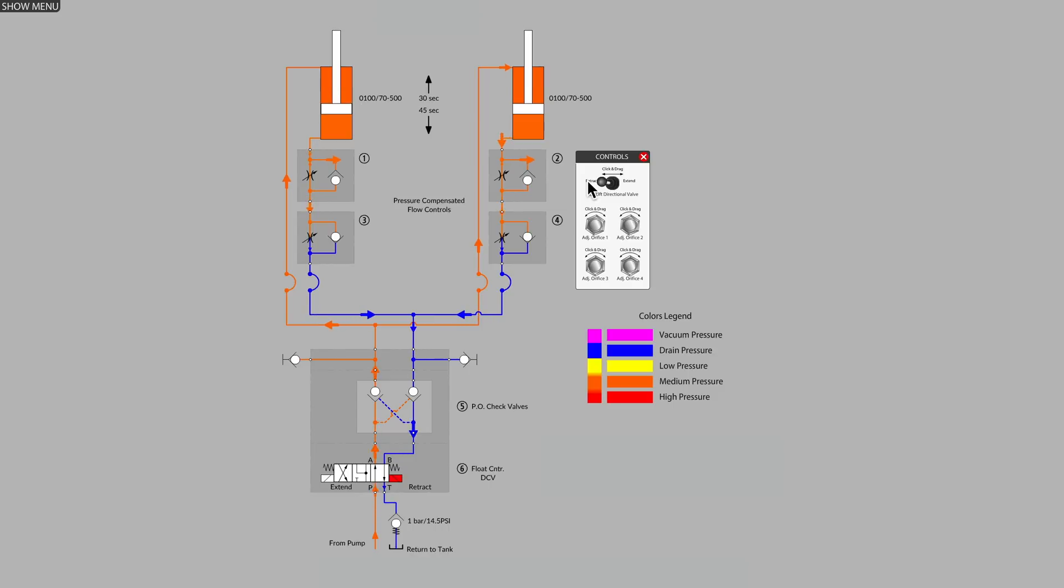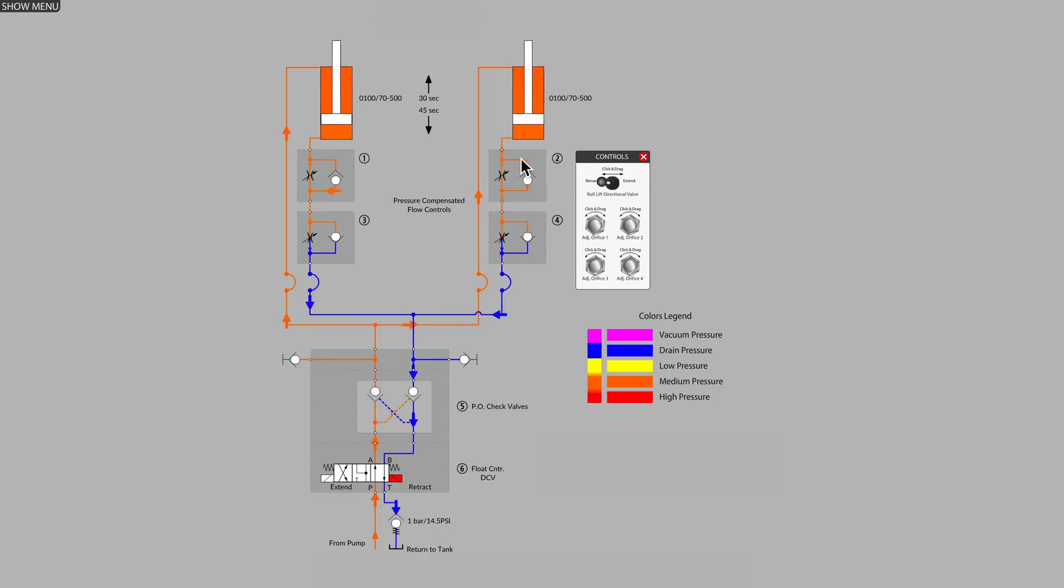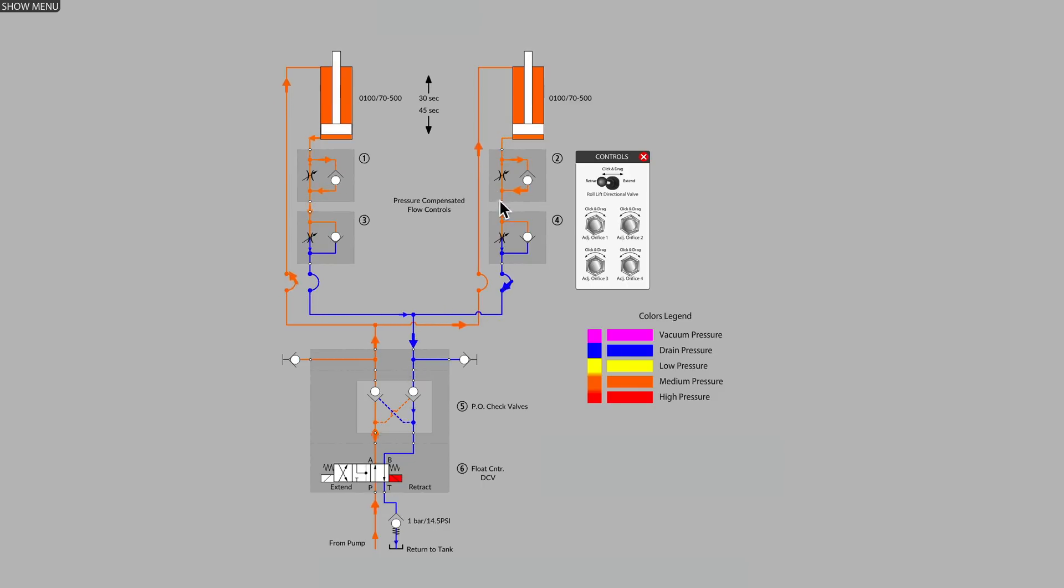What we see now is meter out flow control, where oil coming out of the cylinder bypasses the upper flow control through the check valve and is metered by the lower flow control.